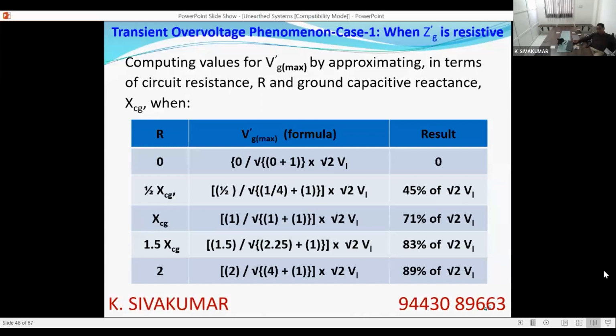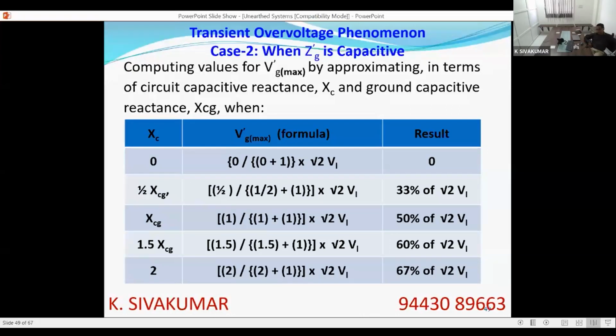Next case is capacitive reactance. Assume that the external impedance is purely capacitive. So instead of R, you put the capacitance XC value. So the denominator is XC plus XCG. They will arithmetically add because they are in the same direction. Here also you put various values for external capacitance. If the external capacitance is 0, if the external capacitance is 50% of the leakage capacitance, 33% voltage. If the external capacitance is 100% of the leakage capacitance, 50% voltage. If the external capacitance is 150%, 60%. If the external capacitance is 200% of the leakage capacitance, 67% voltage.